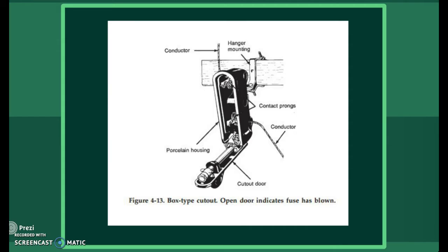The fusible element is enclosed in a fiber tube. When the fuse blows or melts because of excessive current passing through it, the resultant arc attacks the fiber tube, producing a gas which blows out the arc. For this reason, this type of cutout is sometimes also called the explosion type.